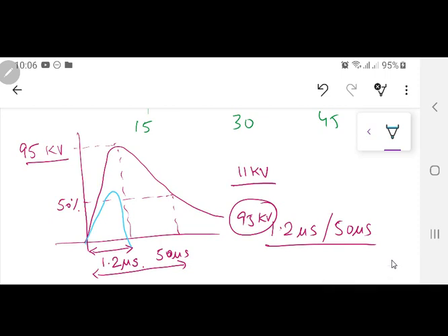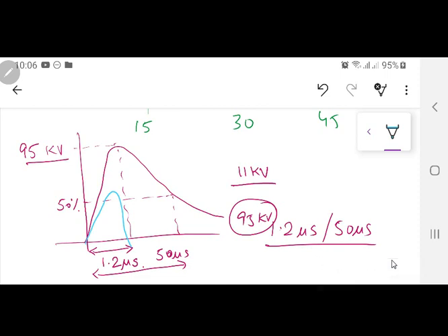Insulator, please, one small point: this is high voltage engineering, not core, but still, since I have taught that course also, high voltage engineering is all about an insulator behaving as a capacitor. Any insulator, if it is a good insulator, will be a very good capacitor, because that means it can withstand that voltage. So for a transformer winding, if it is an 11 kV design, you can somehow increase the input capacitance of that transformer. Then that capacitor is going to be at the front of the winding and it's going to charge, and the whole voltage is not going to be applied to the winding.